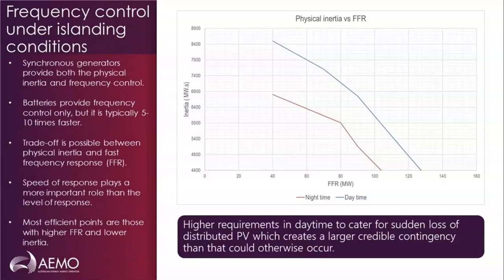So that is more of an efficiency question. As I mentioned earlier, the speed of response is really an important factor. And that's why you can see that we don't have any operating point that corresponds to 0 megawatts of fast frequency response. We have determined a minimum level of fast frequency response that would essentially be needed always in order to be able to arrest a disturbance that could happen within several hundred milliseconds. And we need a source to be able to counter that disturbance within several hundred milliseconds as opposed to several seconds.